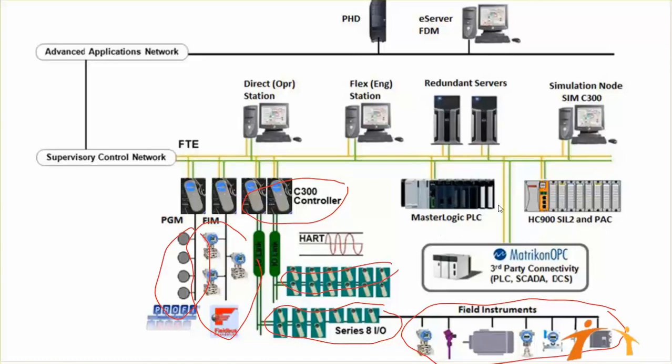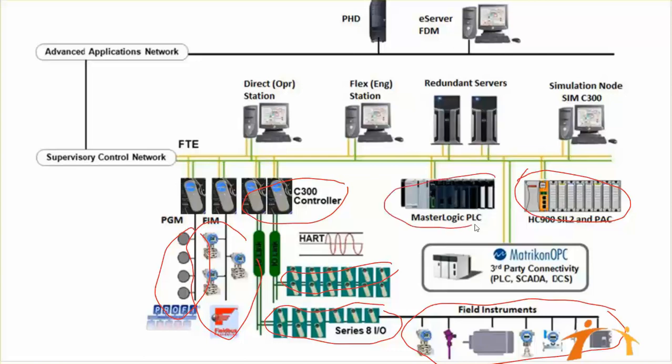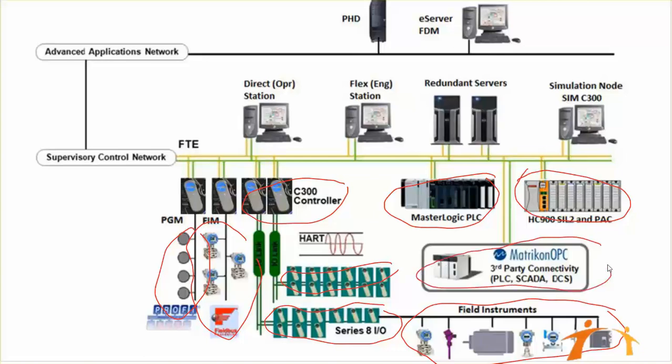At the right side of our architecture, we have Honeywell HC 900 SIL2 PLC and MasterLogic ML 200 PLC, which is also from Honeywell for process control. These can also be connected to our FTE network. There's also another option: you can connect third-party PLCs, DCS, or other things via OPC to our FTE network. So this is our first layer—you connect each and everything to our FTE network.